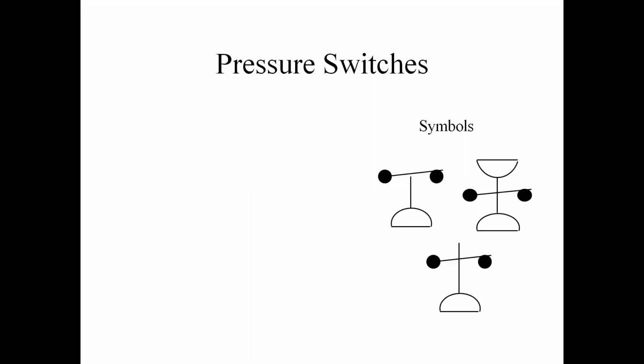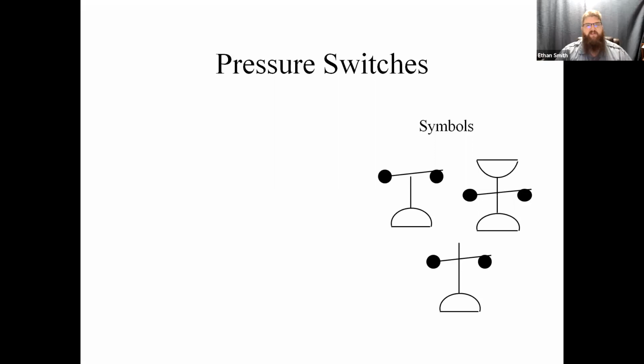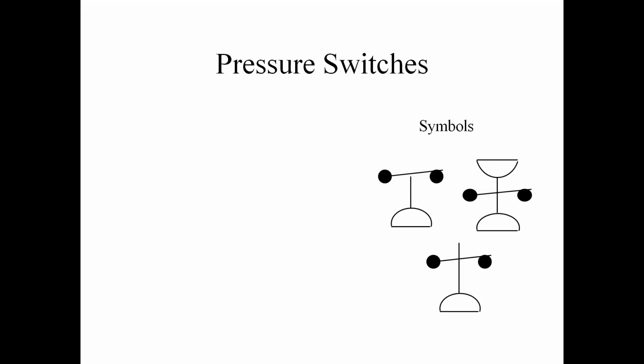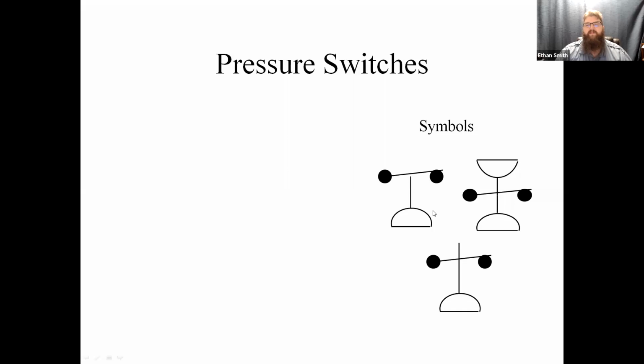Where might you encounter a pressure switch? In the furnace. Furnace has pressure switches for the venter motors. Anywhere else? Condenser units. Yep. Pressure safeties for the refrigeration system. Okay. We got a couple different ones pictured here. We have a single port pressure switch, which just senses pressure from one zone. This would be a normally closed one.